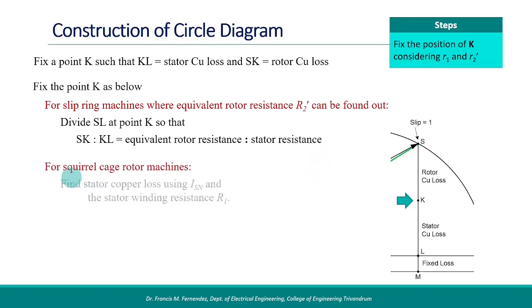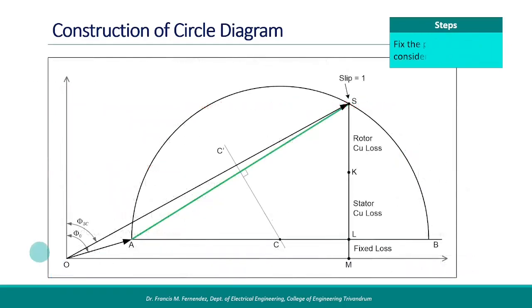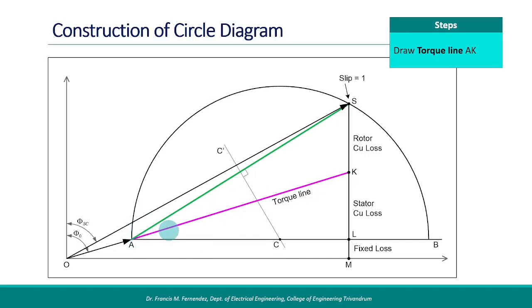For squirrel cage machines, the rotor resistance is not measurable, so we depend on copper losses. First, find the stator copper loss using ISN and stator winding resistance R1. The total copper loss is available from the blocked rotor test data. Then rotor copper loss equals total loss minus stator loss. Mark point K so that the ratio SK to KL equals rotor copper loss to stator copper loss. Remember all these parameters are per-phase values. After marking K, draw a line AK — this line is called the torque line. The line AS is named the output line.